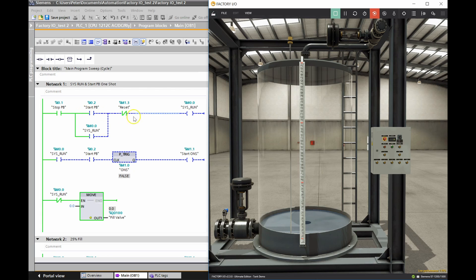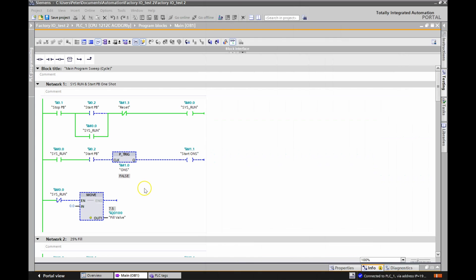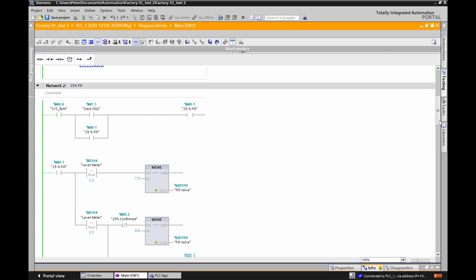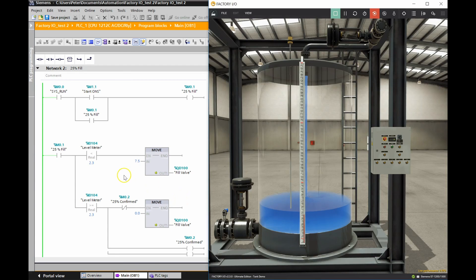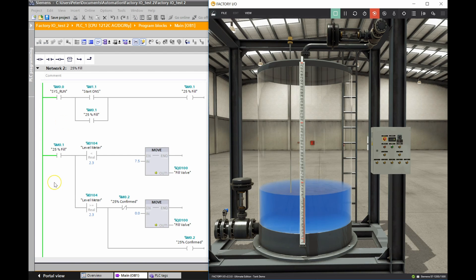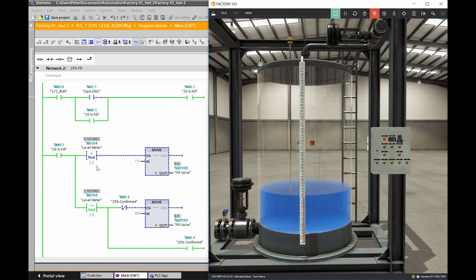Let's hit the start push button - you'll see this kicks in and I'll scroll down to the lower portion of the program. Hitting start should begin incrementing up to 25%. That one shot did come in. Scrolling down to the 25% level: the one shot sent a signal to %M0.1, my memory bit to say I want to go to 25% fill. I have a holding contact, and as long as %M0.1 is true it says send a value of 7.5 to the fill valve.